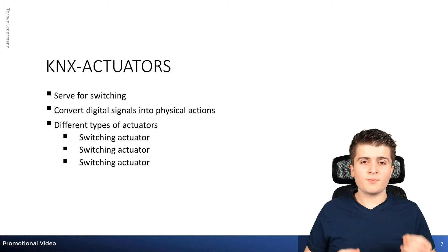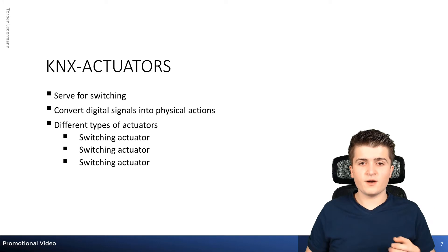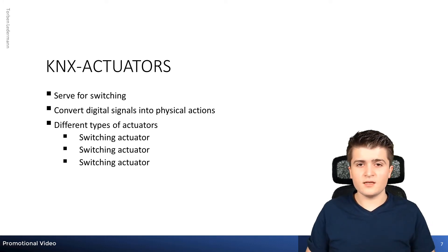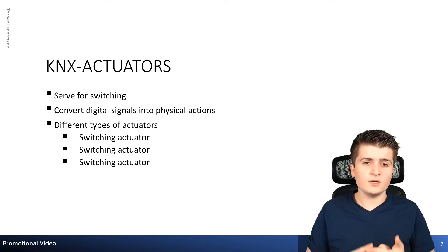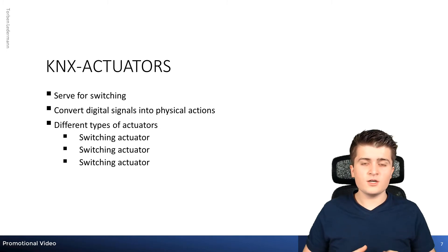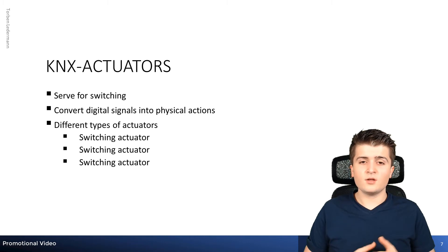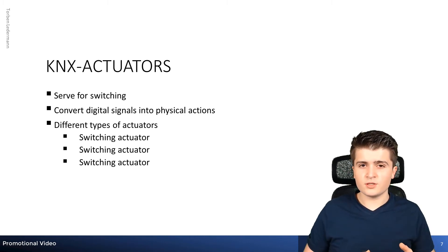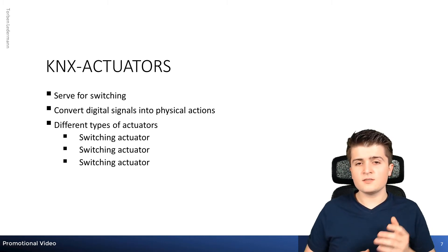It is important that you read the technical information of those actuators so that the functions you need are supported, and that you know details like maximum switching capacity and minimum load for dimming actuators. For a decentralized installation there are also flush-mounted versions of those actuators, which you can install not inside the distribution cabinet but inside the installation box.